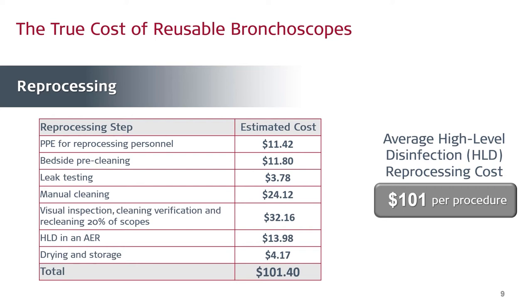You see here the other reprocessing steps and the costs associated with them. Bedside pre-cleaning, just under $12, leak testing, manual cleaning, all have associated costs. And one note here about visual inspection, cleaning verification, and re-cleaning: when a scope is making its way through this reprocessing cycle and someone does a visual inspection and sees that there's an issue with the cleanliness of the scope, it may have to go back through some of the steps in this cycle. Also, when bronchoscopes have been reprocessed and then are in drying and storage for a long period of time, in some cases, they need to go all the way back through the reprocessing cycle to make sure that they are properly disinfected. So lots of costs here.